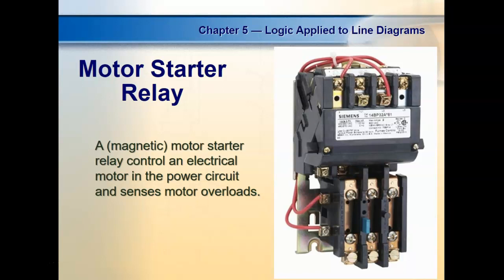We typically rate these right at the threshold for the motor. You don't want to overrate them because if you overrate them, just like if you put a fuse that's too big in, you're begging for trouble. But you also don't want to put something too small in because when the motor starts up, it's got to pull a certain amount of current.